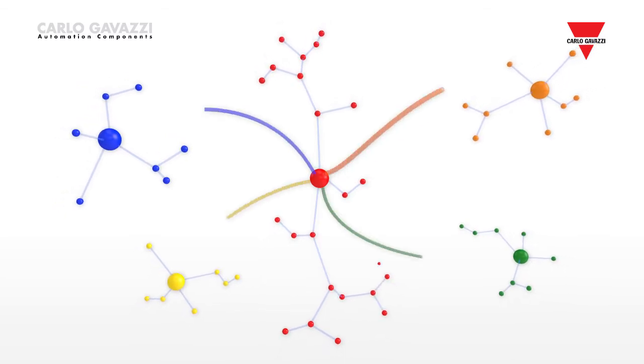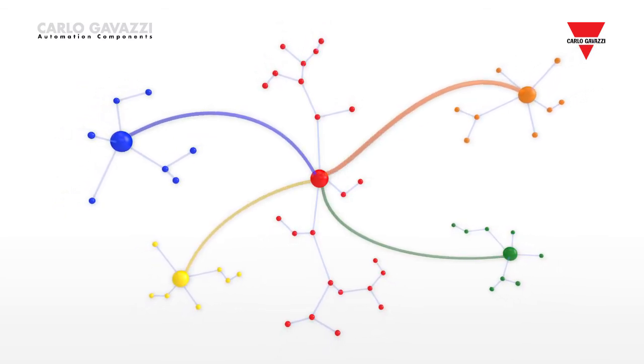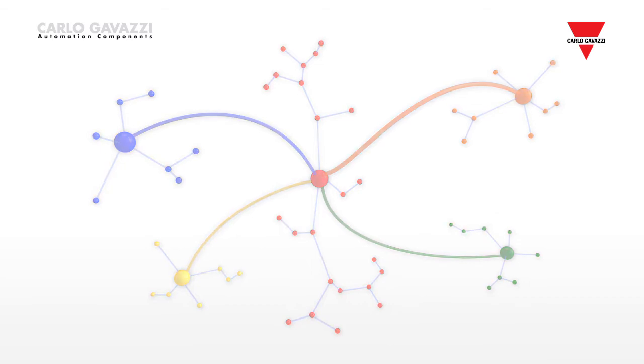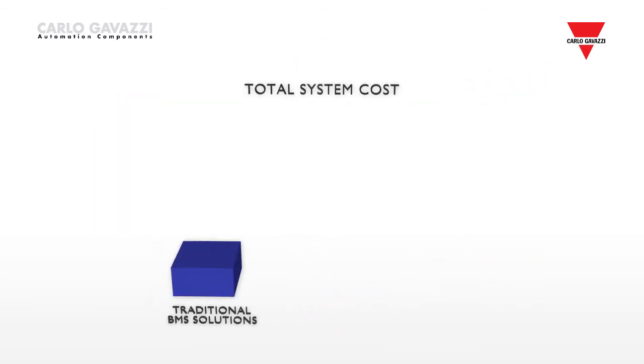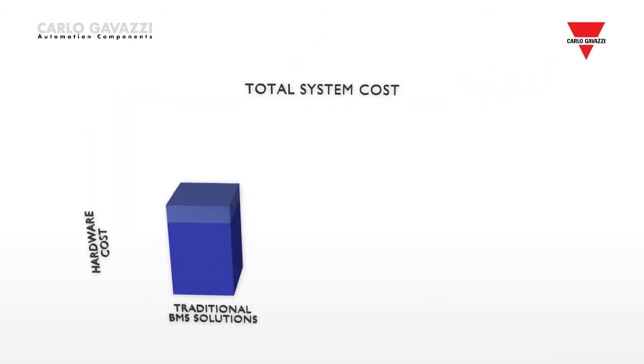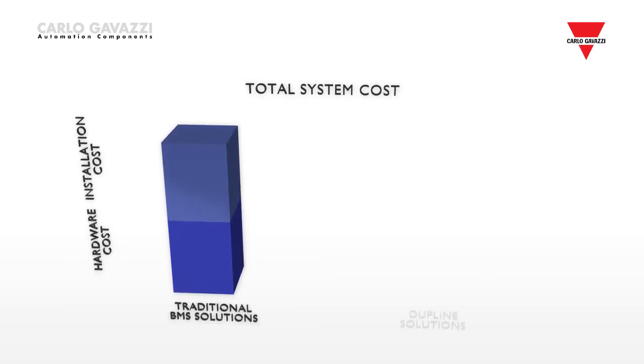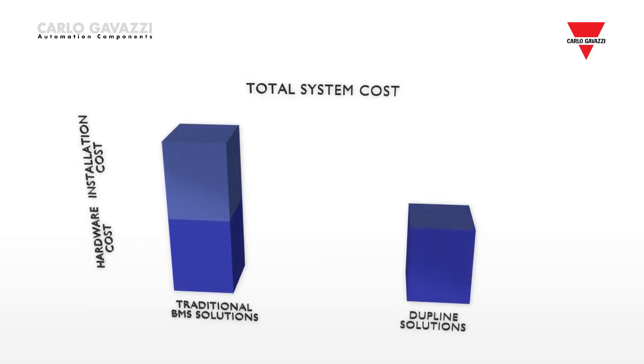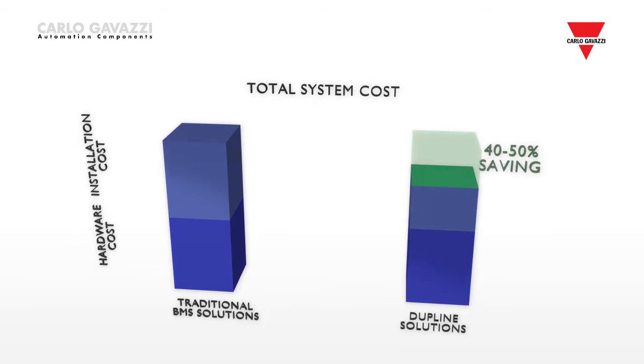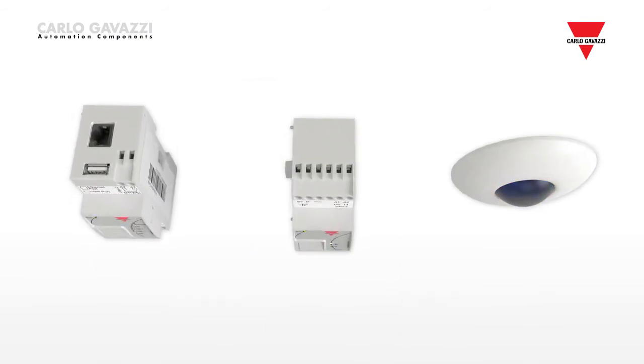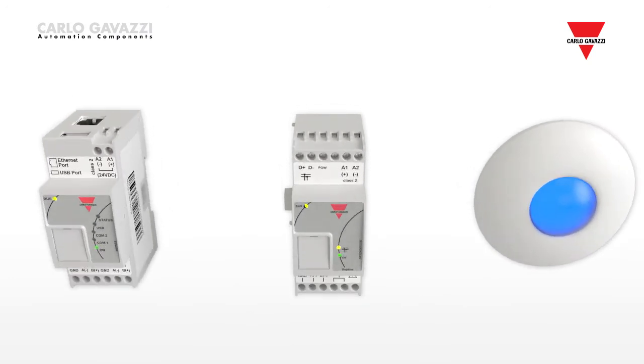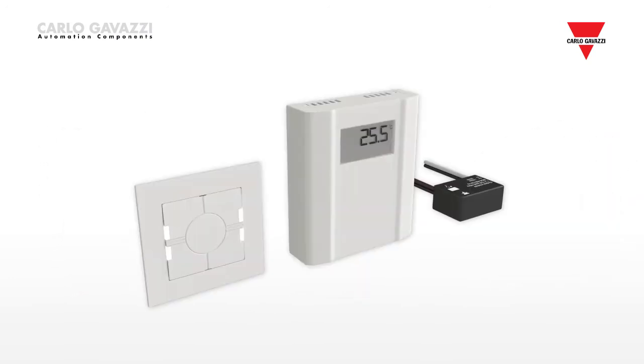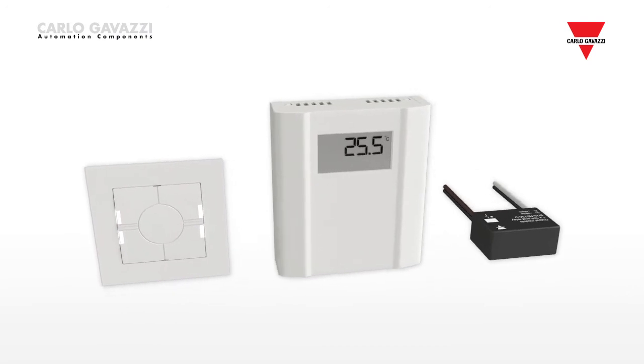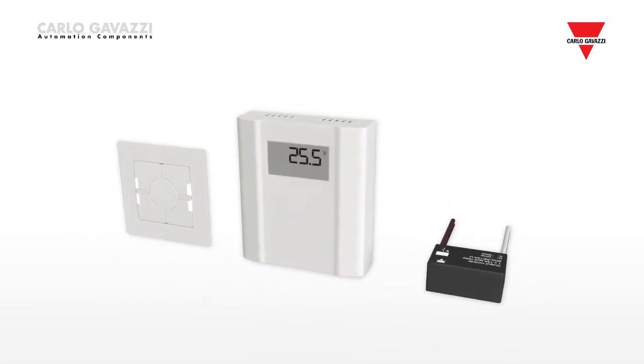The main benefit for system integrators and installers is reduced cost and time. With this new system, installation costs can be reduced by 40 to 50%, while hardware costs are comparable with or less than traditional BMS solutions. Many Dupline components such as presence and movement detectors, CO2 temperature and humidity sensors, lux sensors and small decentral input-output modules are powered by the bus.